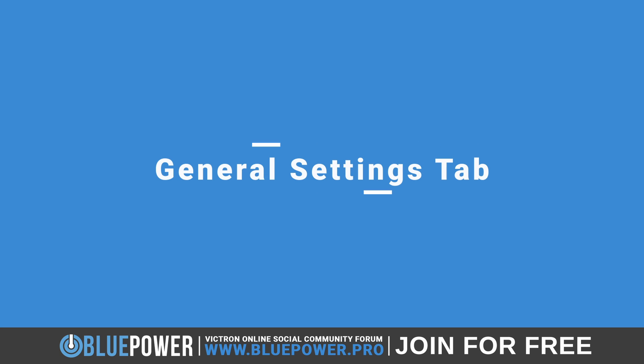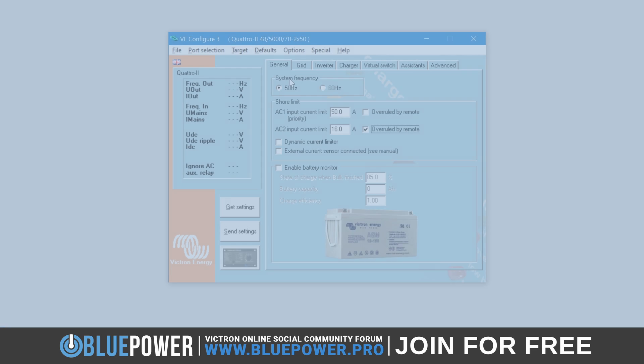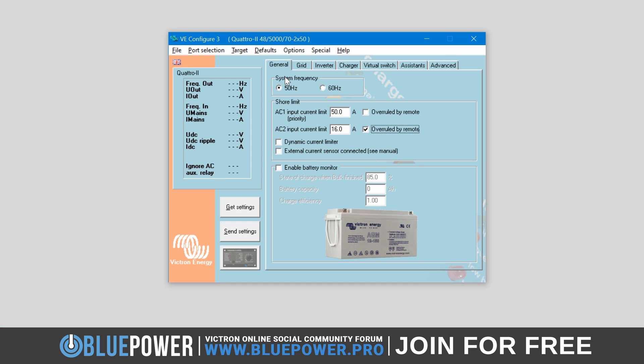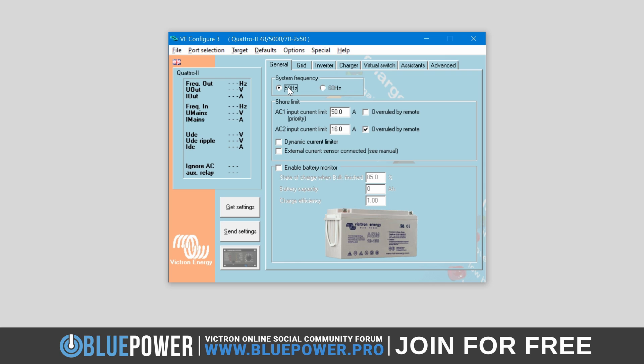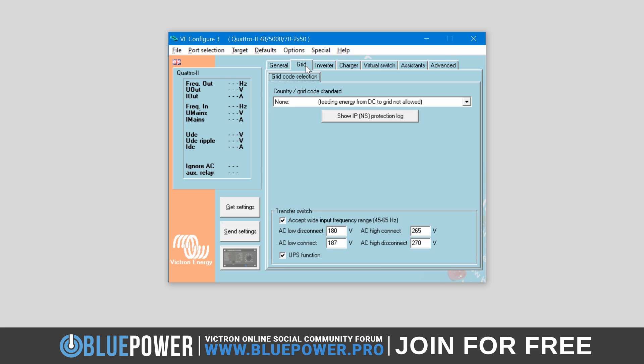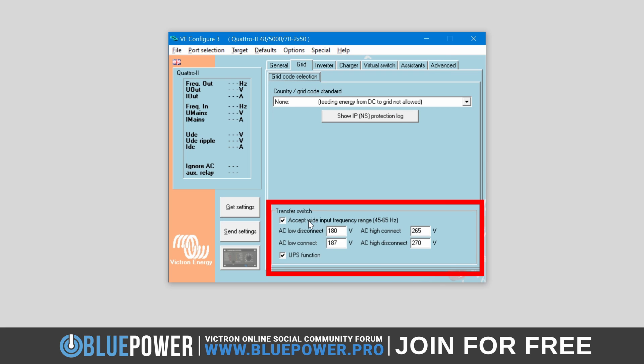Let's take a closer look at the individual settings within each of these tabs, starting with General. The General tab is where you can adjust general incoming AC settings such as system frequency, shore limits, dynamic current limiter, together with the battery monitoring features. Under System Frequency, you can select the frequency of the system — either 50 or 60 hertz. Note that this setting also determines the acceptable frequency range for the transfer switch if the accept wide input frequency range is disabled in the Grid settings tab.